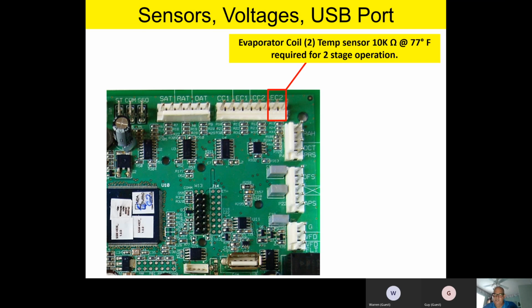So no, if you have a faulty sensor, you're going to have to replace that sensor, and you are not able to jumper that. Thank you for that good question. Because if you jumpered it, it would interpret that as 0 ohms or very low ohms, and then that sensor again would think it's like 300 degrees or something like that. So good question. Any other good questions or comments about that?